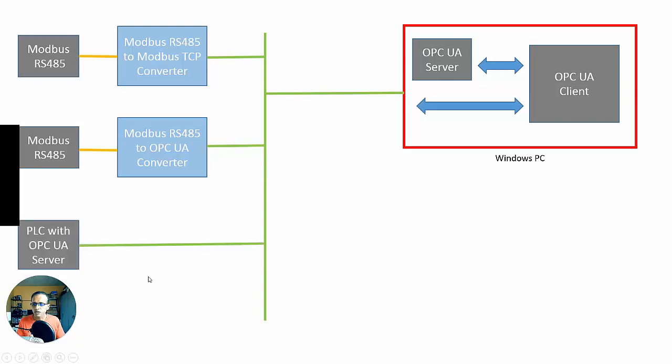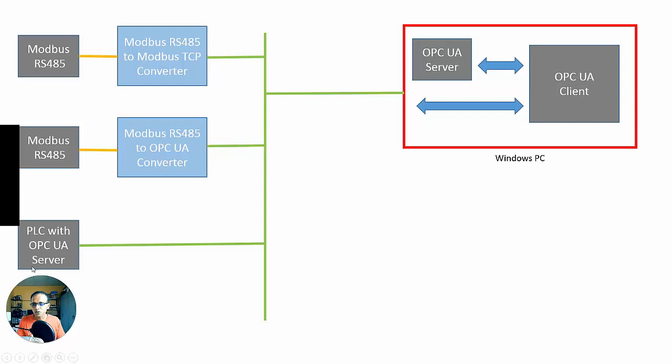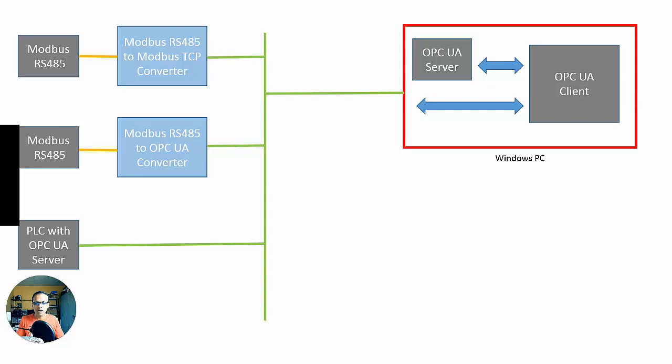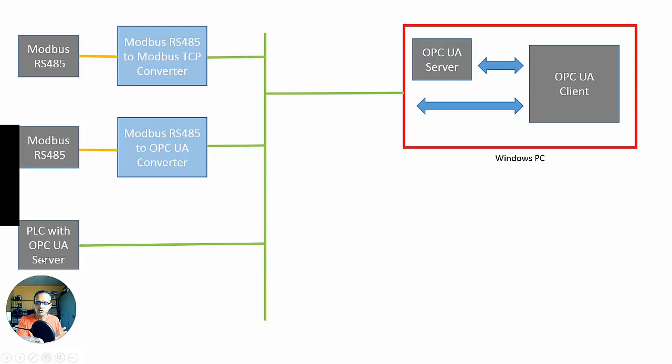You could also have this scenario, a PLC or a VFD or some other device with an OPC UA server built into it. Now, there's no protocol conversion taking place here. What's happening is that when you have this type of device, what the PLC vendor will be doing is that they're writing software, OPC UA software, and expressing their native PLC memory in OPC UA format, the OPC UA data model. So, now the OPC UA client could talk to this PLC via its OPC UA built-in server. So you can have these various scenarios here on the OPC UA server side.